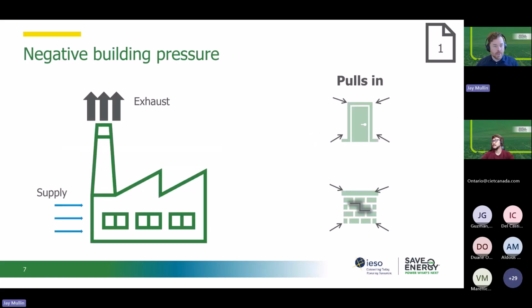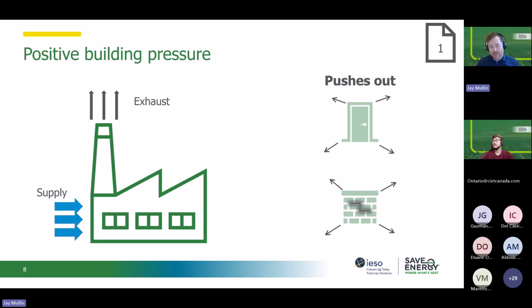So why is this important? Buildings where there is more air being exhausted than is being supplied into the building are going to create a negative pressure within the facility. This is actually pretty common in industrial facilities and means that air is going to be pulled into the building anywhere it can. So that negative pressure is going to be pulling air in. Conversely, when there's more supply air being brought into the building than exhaust air pushing air out, that's going to create positive pressure inside the building that pushes air out of the building wherever it can, either through doors, openings, leaks in the envelope, etc.